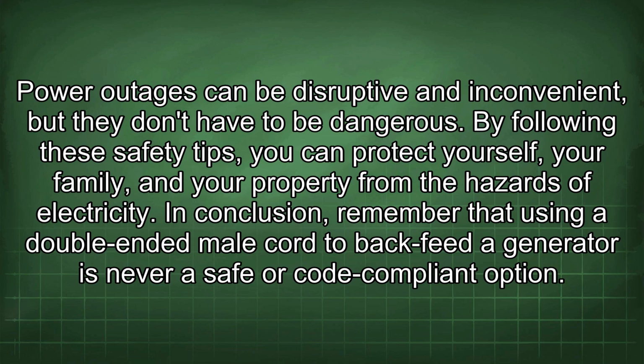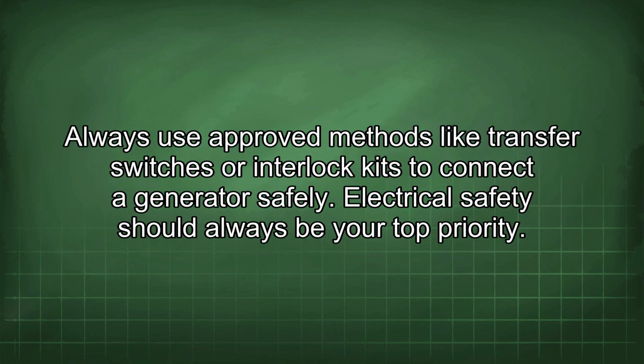In conclusion, remember that using a double-ended male cord to backfeed a generator is never a safe or code-compliant option. Always use approved methods like transfer switches or interlock kits to connect a generator safely. Electrical safety should always be your top priority.